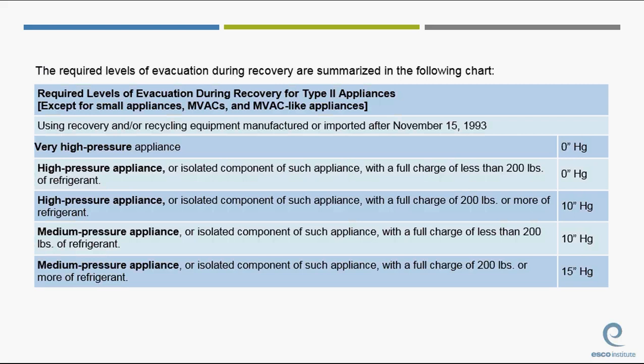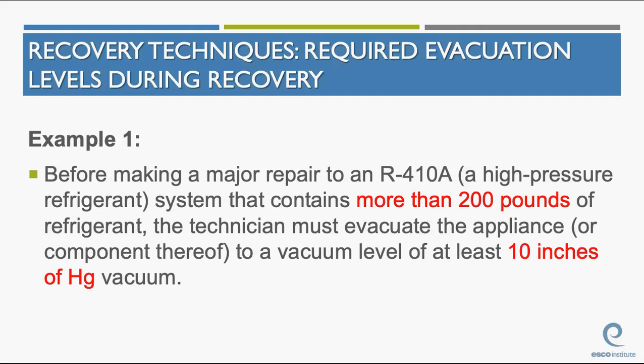R22, it's falling very close to the medium pressures. Look at the top of your refrigerant chart that's at the end of this manual. I'm pretty sure, if not positive, that it tells you the different pressure classifications. Also in the manual it says in example 1 below this chart, before making a major repair to an R410A, a high pressure, Yeah, there you go. Okay. 410A system, it's a high pressure refrigerant, contains more than 200 pounds of refrigerant. The technician must evacuate the appliance to a minimum vacuum level of at least 10 inches mercury of vacuum.